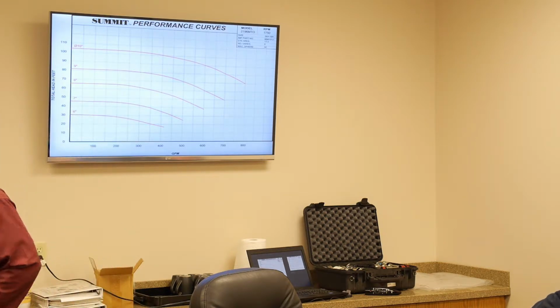And if you look at it, here's a family of curves. All these pumps are represented. We call these families. And this pump will operate in this range at 3,500 RPM. Then you come down here at 1,750 and find the same pump. There it is there. And that gives you a reference point.